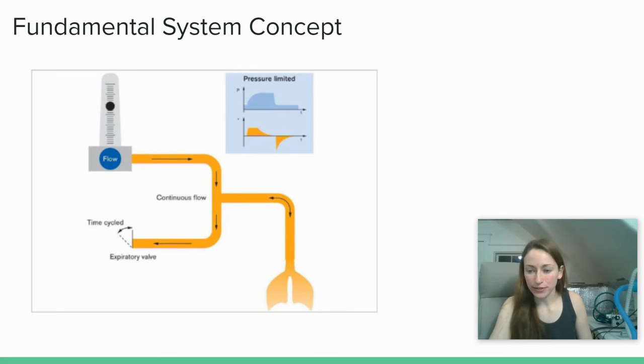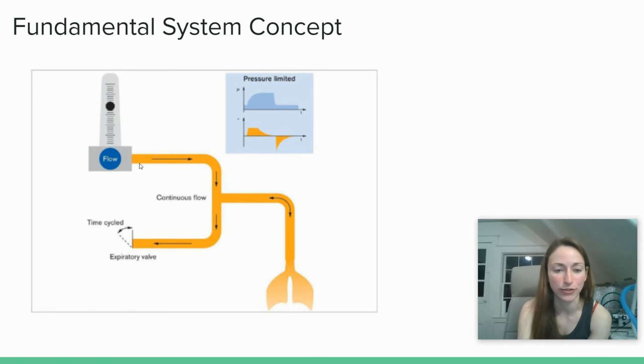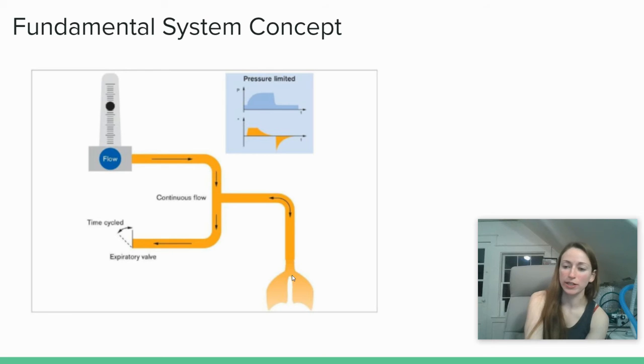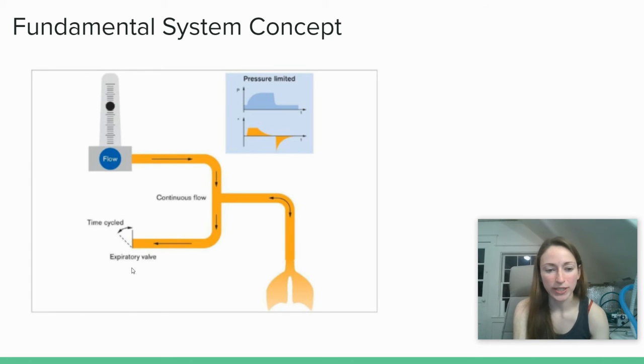Many of the devices out there today, including commercial ventilators, work on this fundamental system concept. If we look at this schematic, we have some aspect of the device which sets the flow. Maybe it does flow limiting and pressure limiting, but it supplies a flow to a device which has a Y circuit. From this Y circuit, there's a part of the circuit that spans to the lungs through the endotracheal tube, and another part which is connected to an expiratory valve. When this expiratory valve is closed and flow is supplied to the system, the lungs begin to inflate. When the expiratory valve is fully open, the lungs are allowed to naturally deflate as a function of the diaphragm compressing.